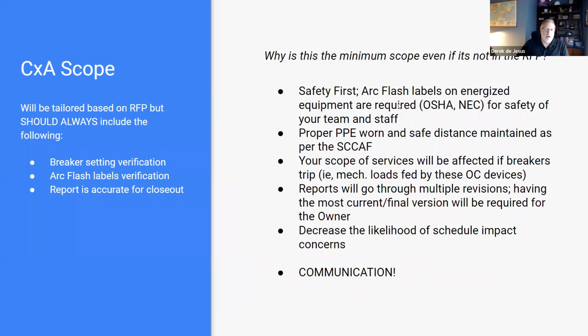Let's just look again at our scope. Even if you're not doing electrical commissioning, you should be verifying that breakers have been set. Who's setting them? Ideally it's the independent testing agent, before they test their breaker or device. Then after they test it, they should apply their label that it's been tested and that it passed.